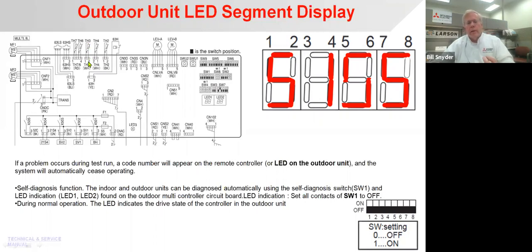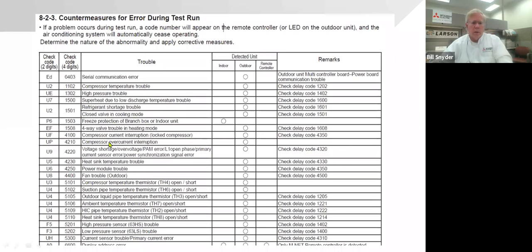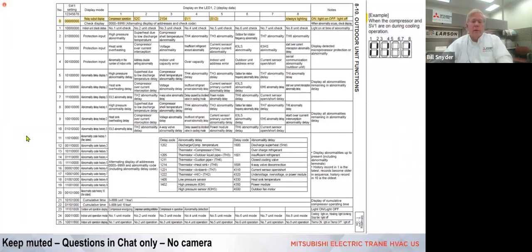Thermistors change resistance as the temperature changes. So if it's bad, it's either open or shorted. If it's got a resistance to it at all, it's probably okay. And I can show you on the service bulletin what that resistance is at any given temperature. But normally I would unplug this and put your ohm meter across it and look for short or open. Believe it or not, these are very fine wires, and in the outdoor unit, I've found them broken many times. Usually it's a rodent, a mouse gets in there and chews on it. So that would tell you what to check, and chances are you will find a broken wire, and you need to replace or repair it.